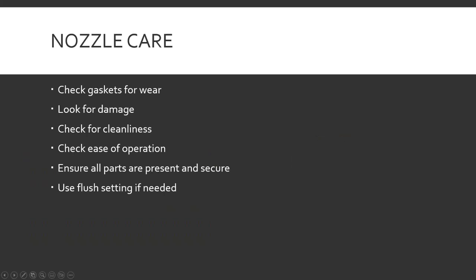Nozzle care: check gaskets for wear — if they're cracked or missing, replace them. Look for damage, make sure they're clean and not covered in mud, dirt, or soot. Check for ease of operation — make sure you can rotate through straight stream to fog pattern, and the valve opens nice and easy without having to really fight it. Make sure all parts are present and secure, and the pistol grip isn't loose. If you have a fog nozzle with debris or grit in it, use the flush setting to try and flush it out.